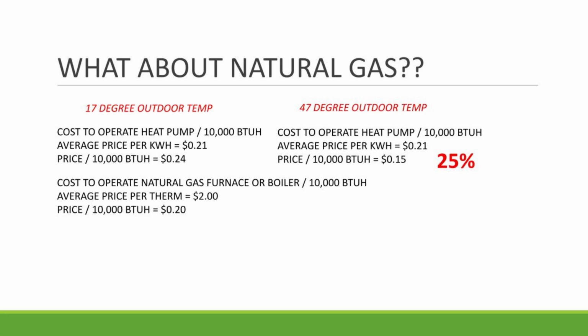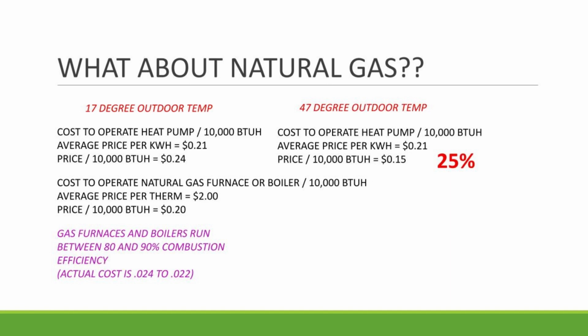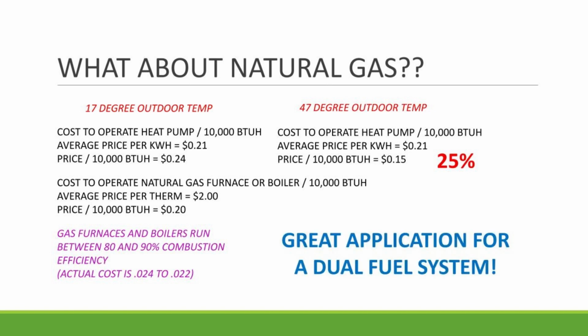Okay. But what about at 47 degrees? Again, as the outdoor temperature climbs, the efficiency of our heat pump will increase, and we'll see definitely a savings there. Now, the other thing to consider is gas furnaces and boilers run about 80 to 90% combustion efficiency. So the actual costs are probably more like 22 to 24 cents. So even at 17 degrees, it's still cost effective to operate the heat pump. And it's really a great application for a dual fuel type system, where I have the option to do either or.